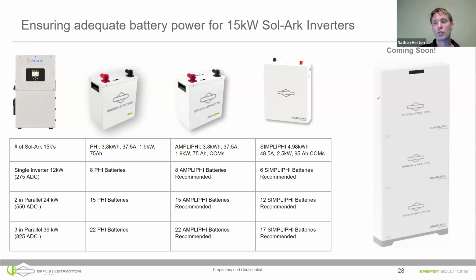So the output of a 20 kilowatt hour bank like this is going to have significantly more than 10 kilowatts of output. But I don't have that exact spec for you yet, so I'm not going to give it. The Phi battery on the left side of the screen is a 75 amp hour battery. It's capable of C/2, so it's half of that 75 amps in an hour. So it's delivering 37.5 amps.